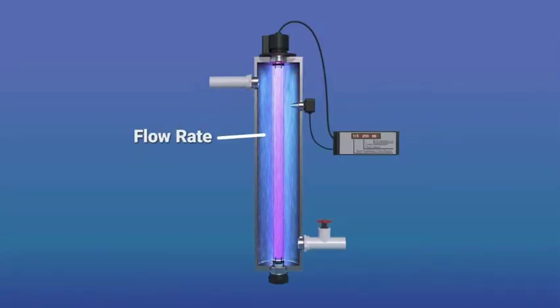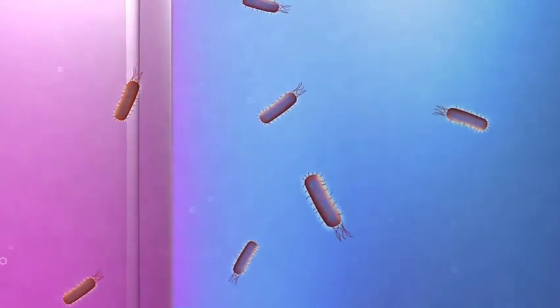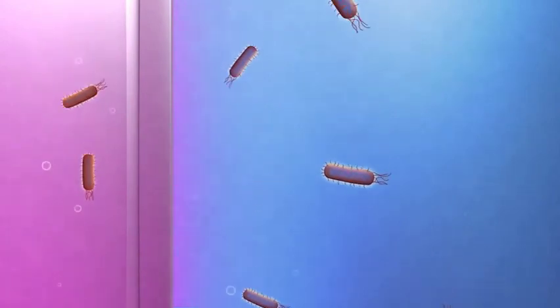Because cells have to be exposed to enough light, it's important to control flow rate and make sure all water is exposed for enough time. If water flows too quickly, UV light can't disinfect it.